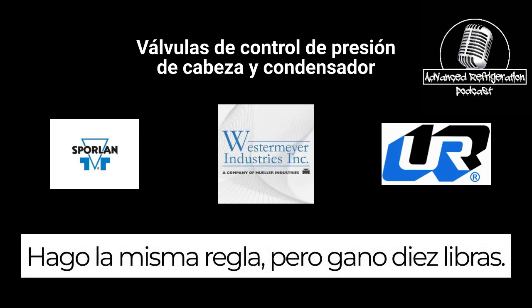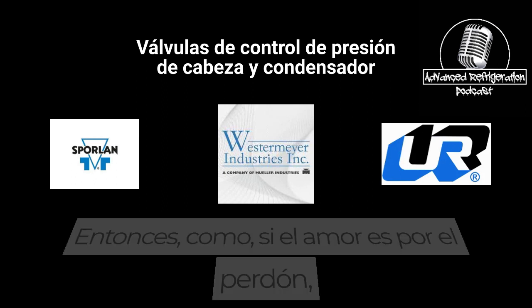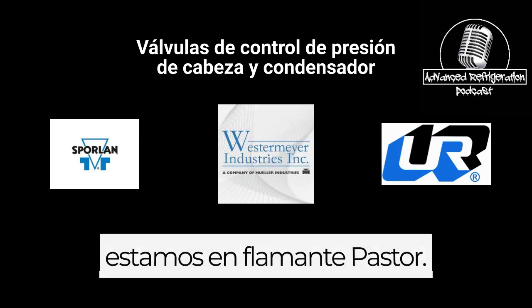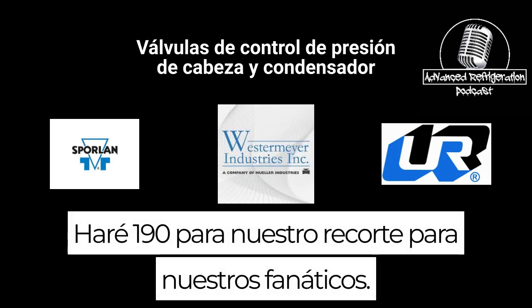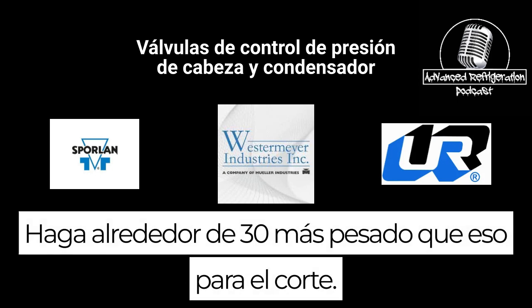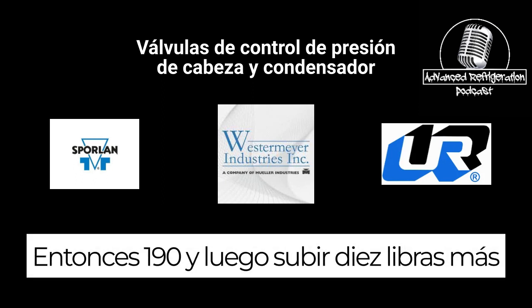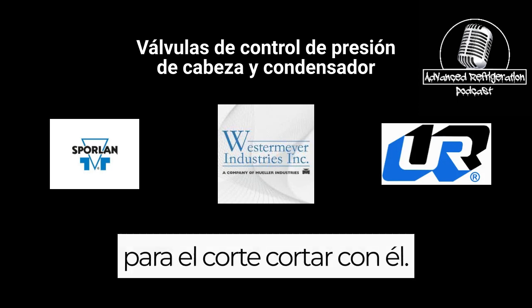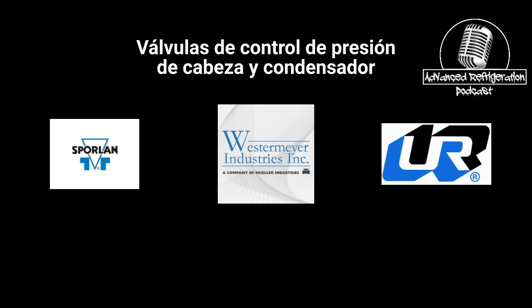And I do the same rule, but I do 10 pounds. So for argument's sake, if we're at 160 on the head pressure, I'll do 190 for our cut-in for our fans. Do about 30 pounds heavier than that for the cut in. So 190, and then go 10 pounds higher for the cutout with it. Yeah.